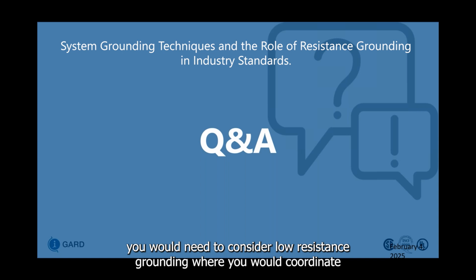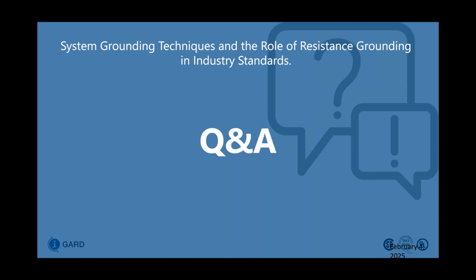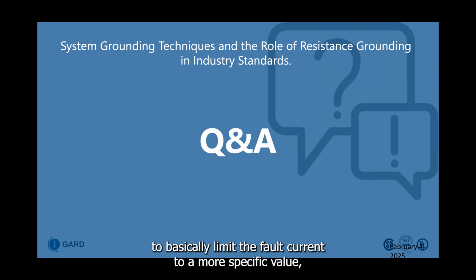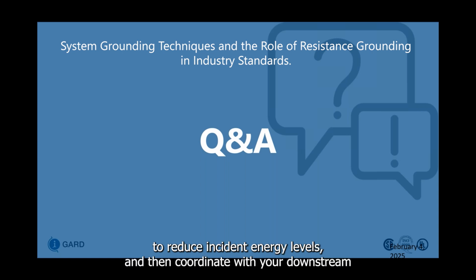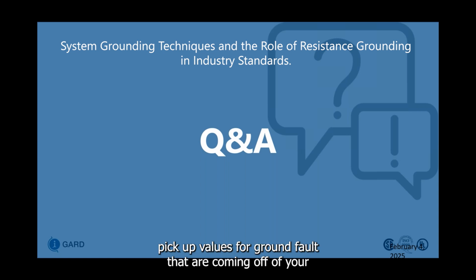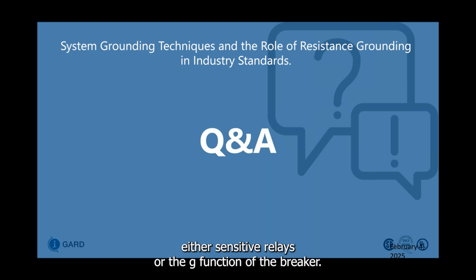As you get to systems that are greater than 5 kV, you would need to consider low resistance grounding, where you would coordinate with your fault protection scheme at the feeder level to basically limit the fault current to a more specific value to reduce incident energy levels, and then coordinate with your downstream pickup values for ground fault that are coming off of either your sensitive relays or the G function of the breaker if you're utilizing that still.